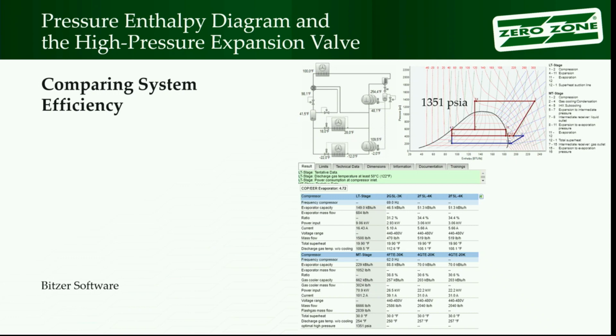So you see that the calculations, a lot of times with CO2, you'll be in absolute units with PSIA. If you want to have gauge converted to PSIA, you add 14.7. Right? You think about that, gauge to absolute, you add 14.7. So gauges always read 0, but we actually know that air is pressing down on us, so we add 14.7 to that.